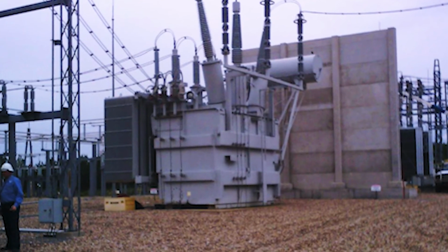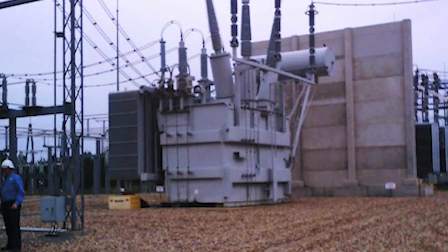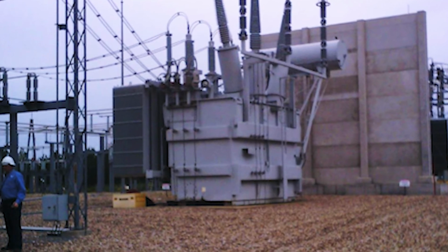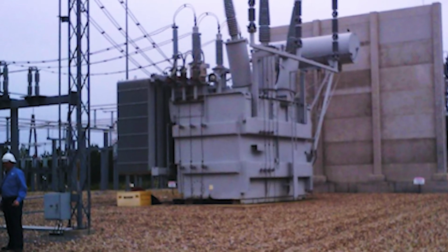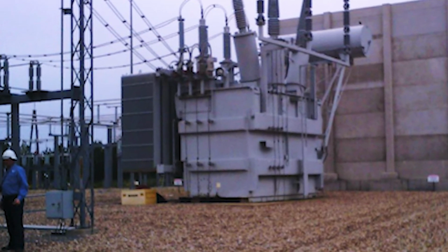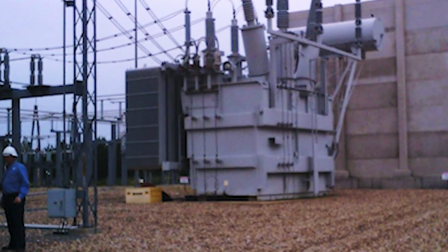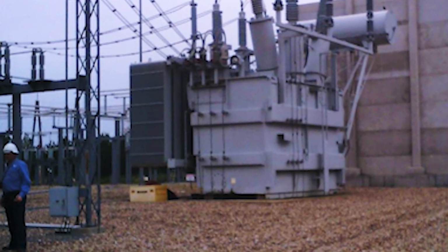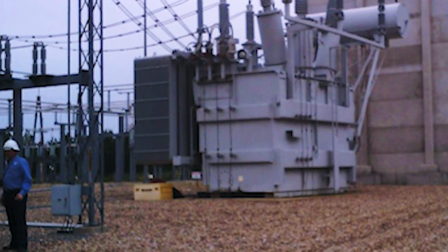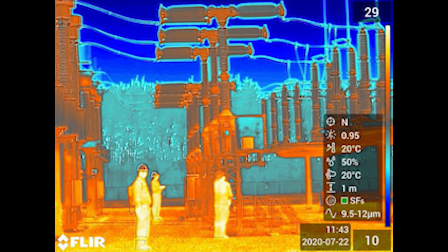This is the same transformer in full spectrum, and you can see me standing there for scale. The bushings on the top of the transformer are about 55 feet to the top from the ground. Elton was trying to take a full spectrum picture for reference, and we were documenting what we were seeing in infrared and with the sonic camera. The hottest thing in this photo are the people. No hot spots here. This is another good reference photo, as we know the body temperature is around 35 degrees Celsius. We moved over to the other side of the substation.